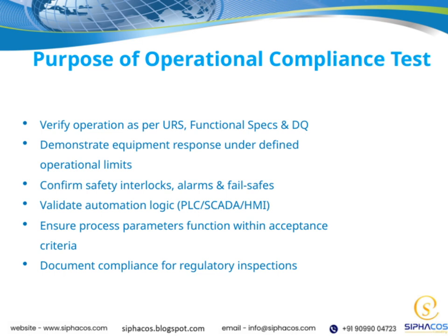Additionally, we need to validate the automation logic, including PLCs, SCADA systems, and HMI interfaces, to make sure they operate seamlessly and correctly. Another key point is ensuring that process parameters stay within the acceptance criteria, which helps maintain product quality and process stability.